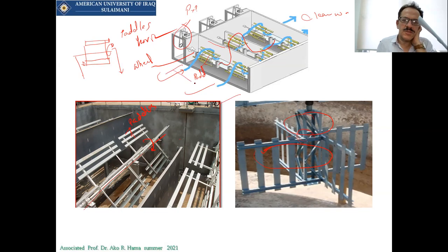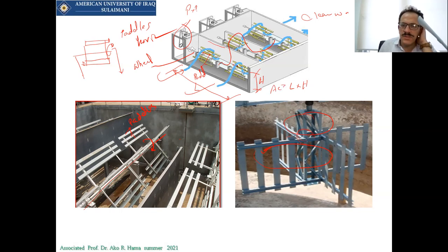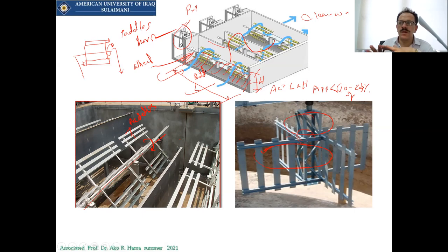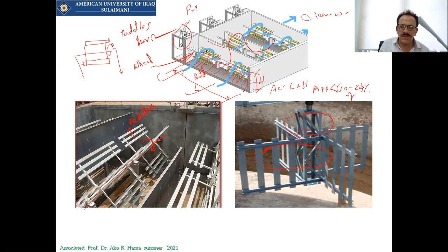The area of the paddles should be 10 to 20% only of the whole cross-sectional area, so the water goes through the paddles and is mixed. We need to know how much power is required for this rotation. We also need the volume. The volume depends on G. G equals the square root of P divided by (volume × μ), and G is between 10 to 80 per second.